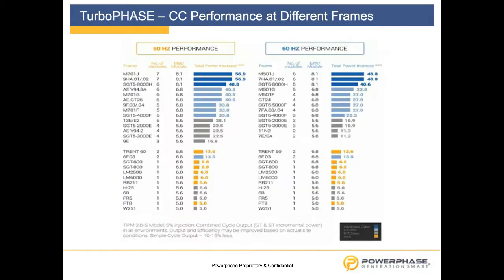The last slide I would like to present is the Turbophase performance in combined cycle at several major frames, on the 50 cycle and on the 60 cycle performance. So you can pick whatever gas turbine, in open cycle or combined cycle. For example, on a 9E, we would add 16.9 megawatt with 3 of our Turbophase modules. That shows the performance and the flexibility of our modules.